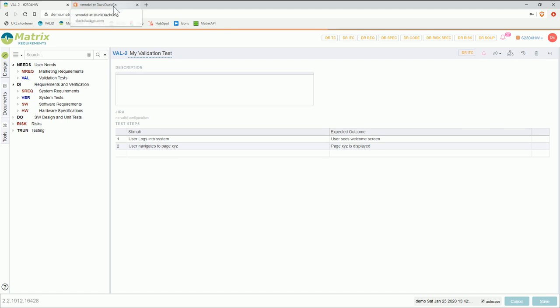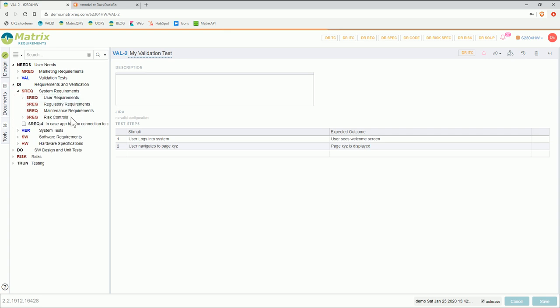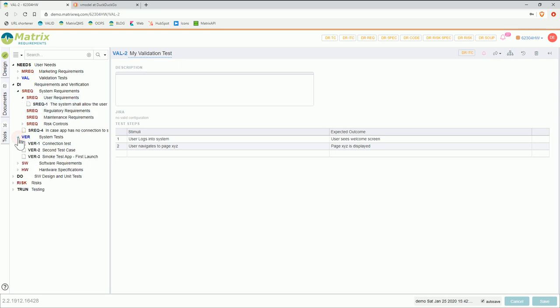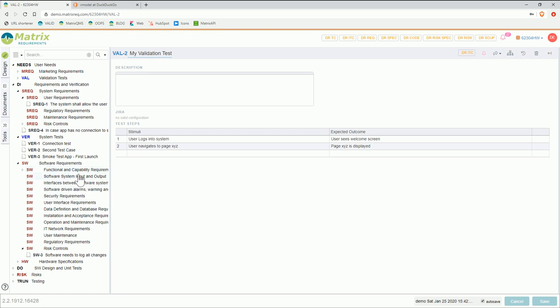If you look at the V-model there are lots more layers, and these other layers could be for example system requirements. Again you can order them in a tree structure, and along with the system requirements usually go system tests. Then if I go down one level I would have software requirements, and there are also standards like IEC 62304 which tells you what kind of requirements you should think about and document, so all of that could go in here.